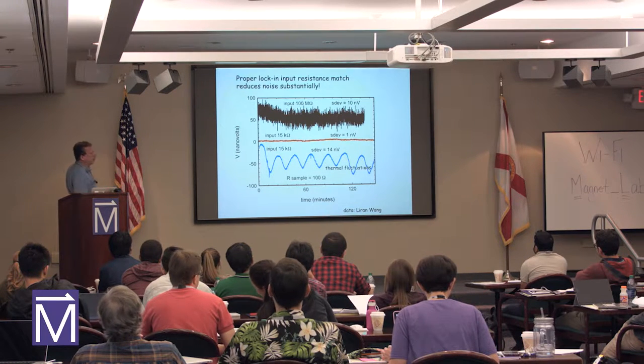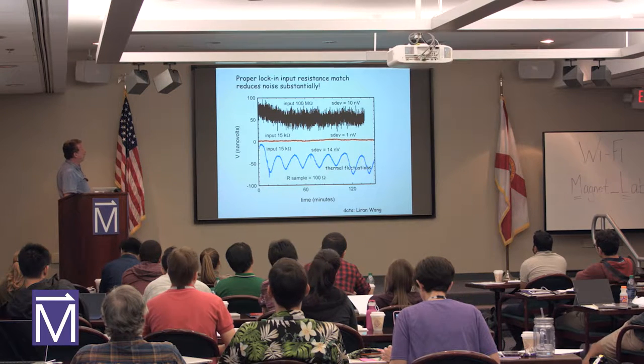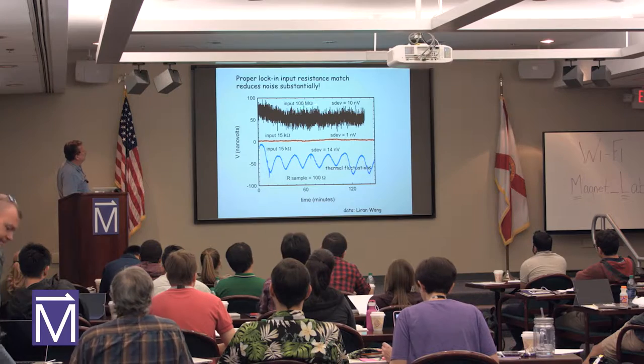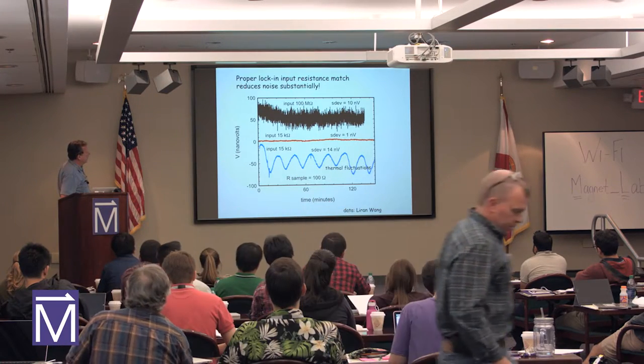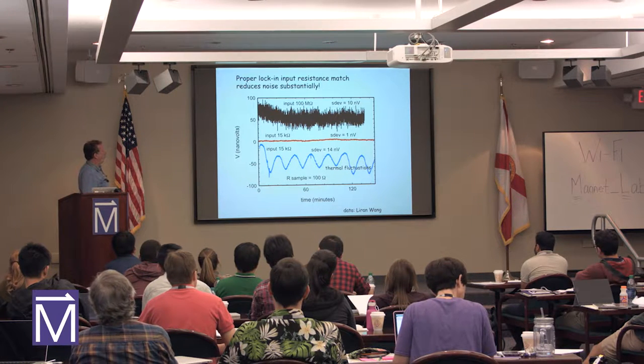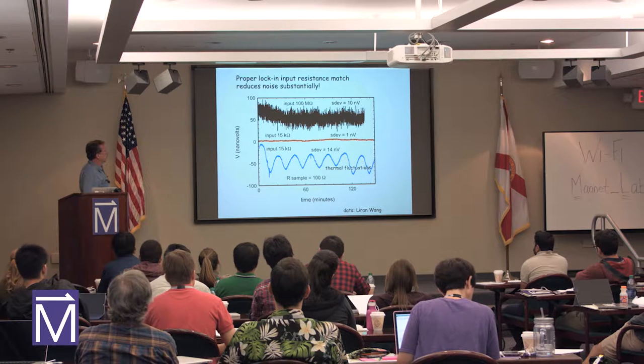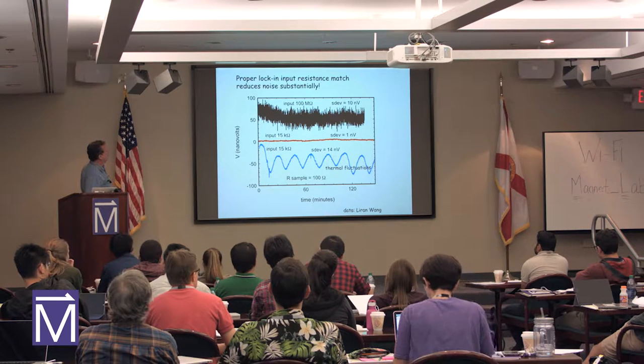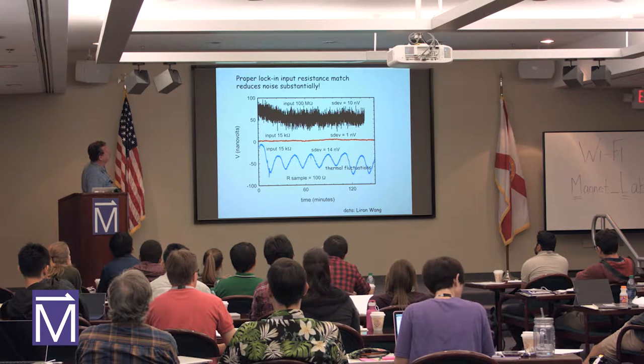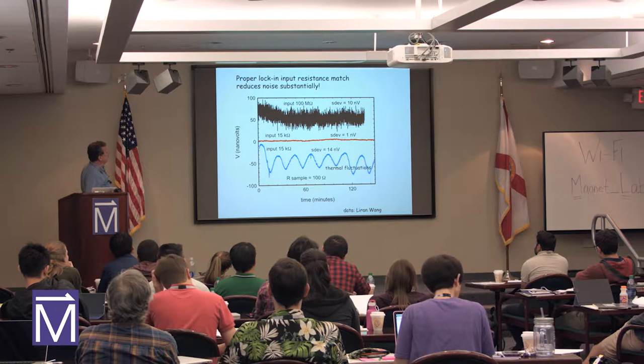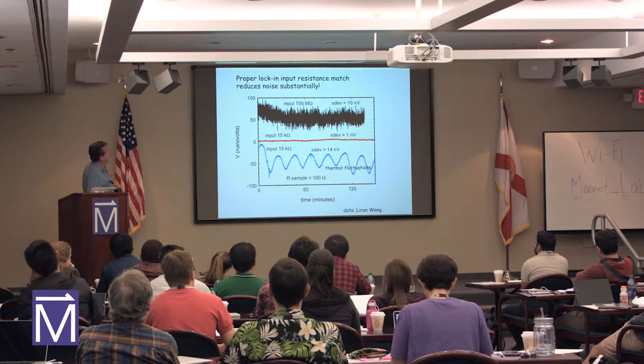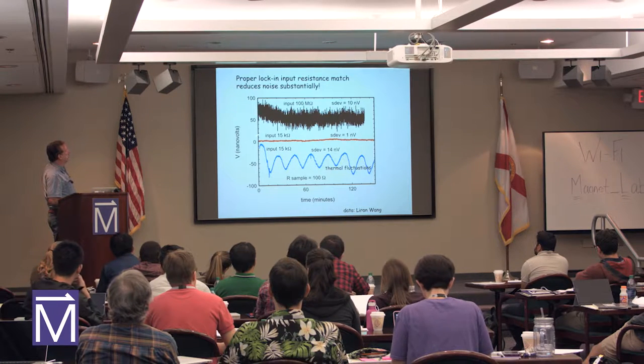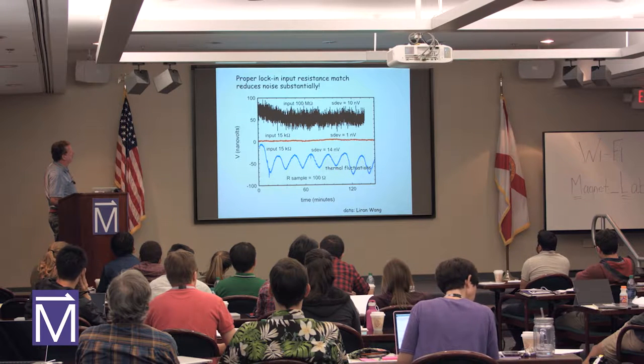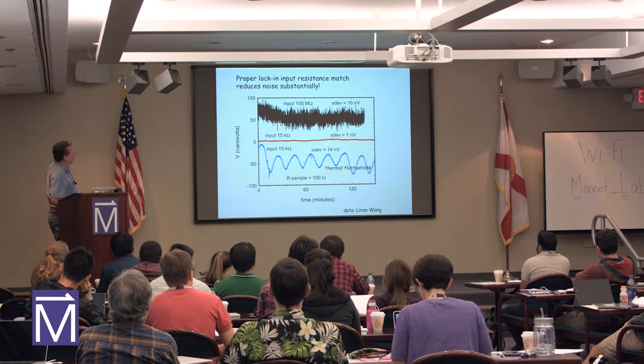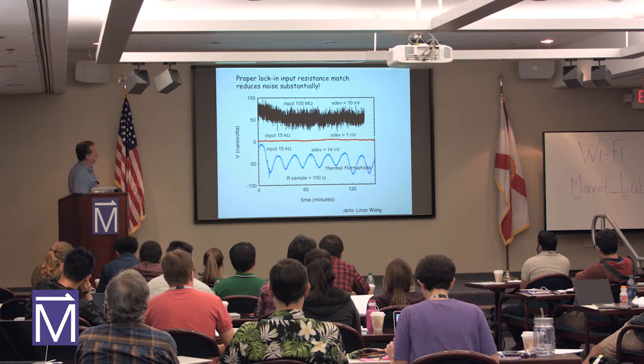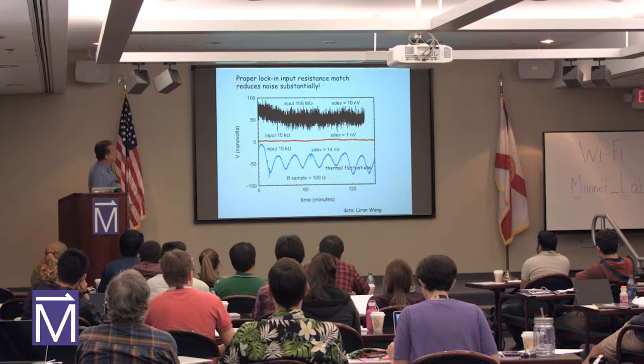So this was an experiment on the table, not any cryostat involved. Measurement on something like 100 ohm. This was a resistance bridge, so the sample was like 100 ohm. And as you can see, when we use a 100 mega-ohm input, the noise is as high as 10 nanovolt standard deviation. When we use a proper lock-in input, like 15 kilo-ohms, it's reduced 10 times. So it's very substantial, and we measure almost 1 nanovolt. But this was measured in an enclosure.